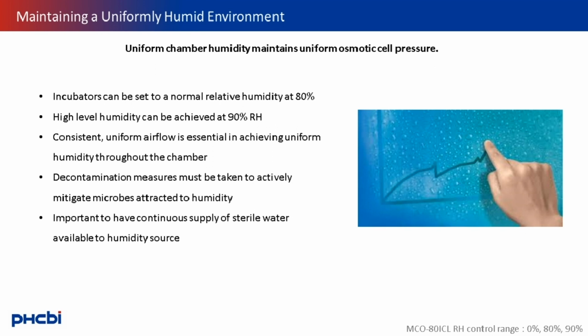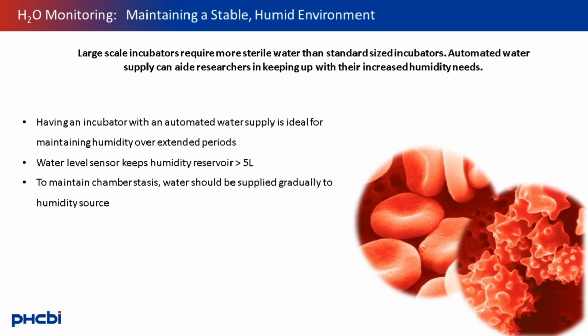While important to cell function, humidity attracts unwanted contaminants. It's important that all humidity sources are kept clean and mitigate possible contamination. It's also important to have humidity control for changes in humidification requirements brought on by large-scale apparatuses. Because humidity is so important to maintaining healthy cells, it is important to always make sure that the humidity source is amply supplied with water.